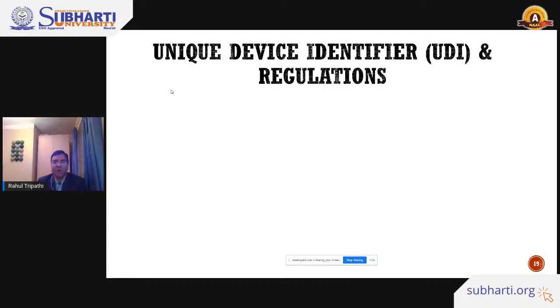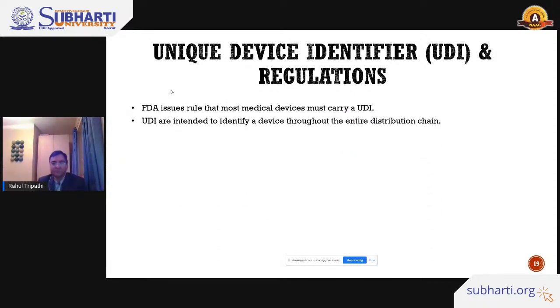The foremost important thing in the medical device segment is UDI. Remember the short term UDI, which is unique device identifier. It's a global identifier, and it is provided by third parties, not by the FDA. The unique device identifier is needed for class 1, class 2, class 3, all kinds of medical devices. Now, the FDA issued a rule that most medical devices must carry a UDI, the unique device identifier.